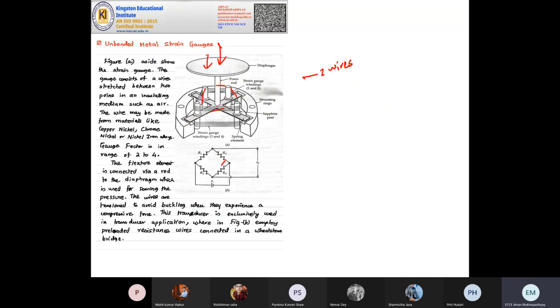There are 4 wires forming this Wheatstone bridge. When there is no strain, these 4 wires are balanced, the resistances are balanced, and the output is 0. But when you apply some force on this diaphragm, 2 of these wires will experience an expanding force, say plus, and the other 2 will experience a contracting force. This causes the Wheatstone bridge to become unbalanced, causing an output voltage to appear, which is proportional to the force or pressure applied on this diaphragm. That is the basic principle. This system has a gauge factor of 2 to 4.